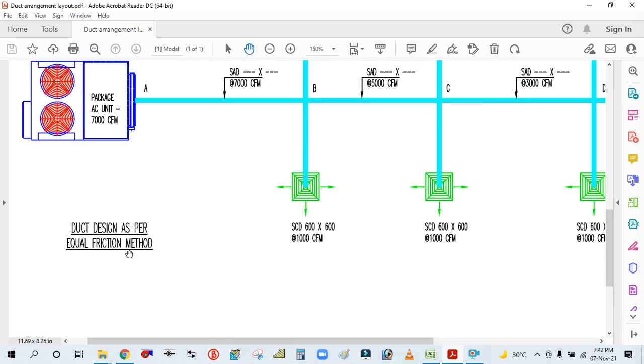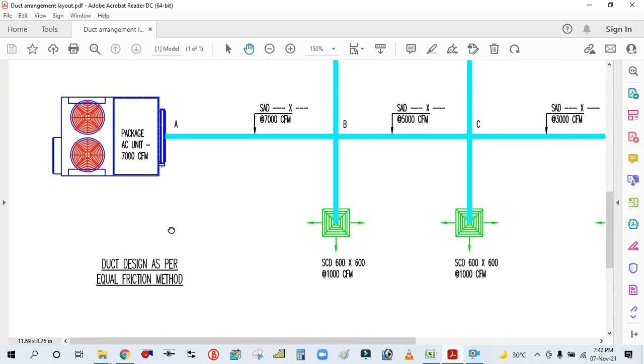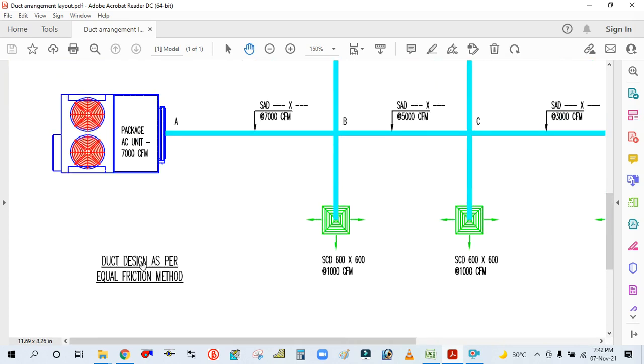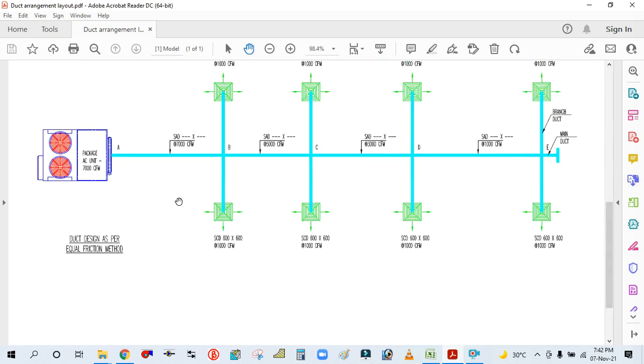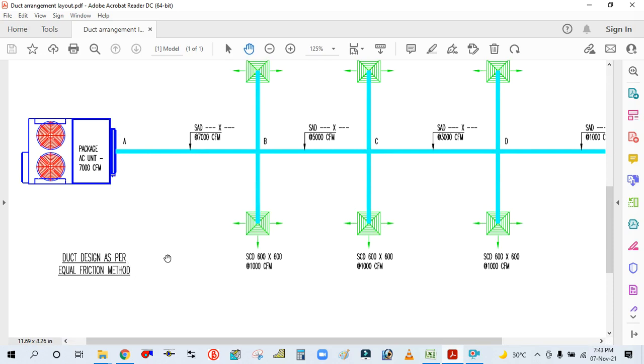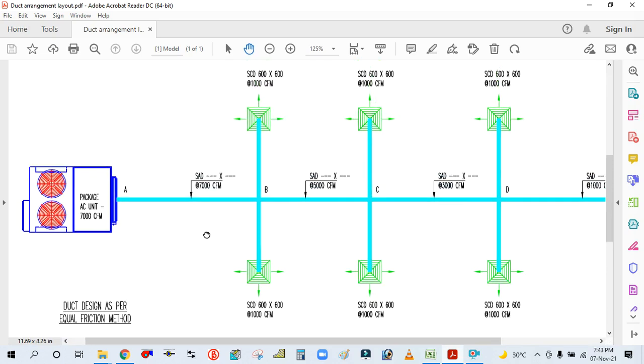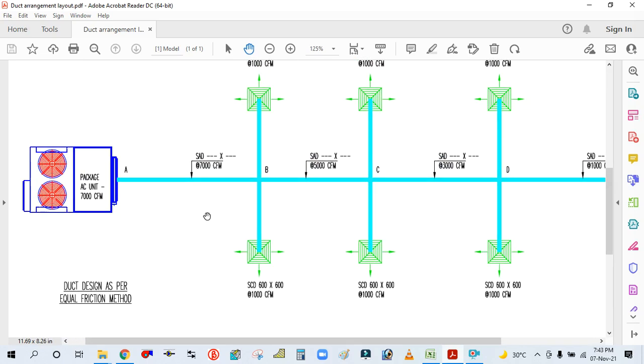There are three methods of duct designing: the equal friction method, the constant velocity method, and the static regain method. The first method — equal friction method — is what we use most in actual practice, generally for commercial and residential buildings. So let's start now on how to size and design the duct.